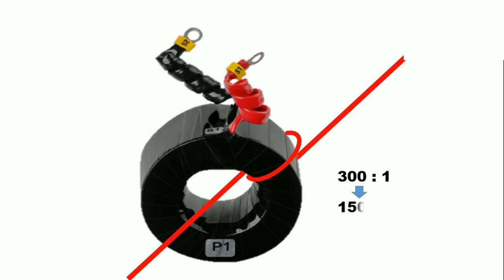Now the ratio will be reduced. The ratio of our CT was 300 by 1, now it becomes 150 by 1. We made one turn of wire around the CT, so the ratio becomes 150 by 1.